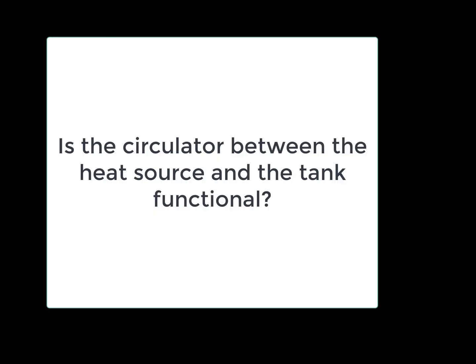Is the circulator between the heat source and the storage tank functional? This is a critical component. If the pump is not moving water between the heat source and the heat exchanger in the storage tank, you will have no heat transfer. Do not depend upon the small little spinny tool that's basically showing you that the windings have an electrical charge, but it does not necessarily indicate that the pump is moving any fluid. That has to be diagnosed and assessed by looking at the temperature differential between the supply and the return.